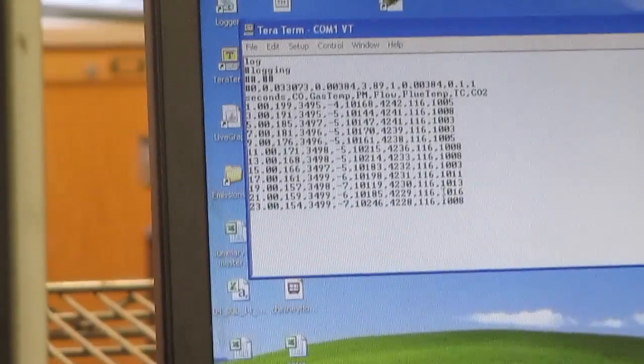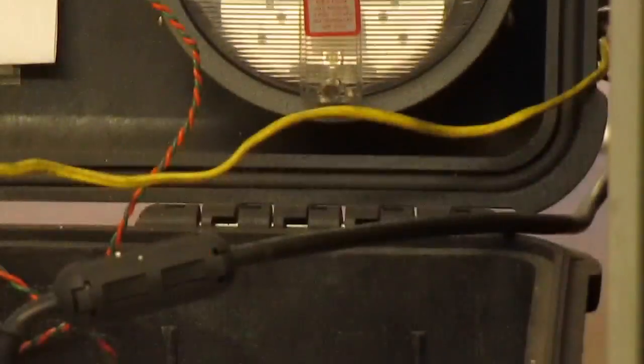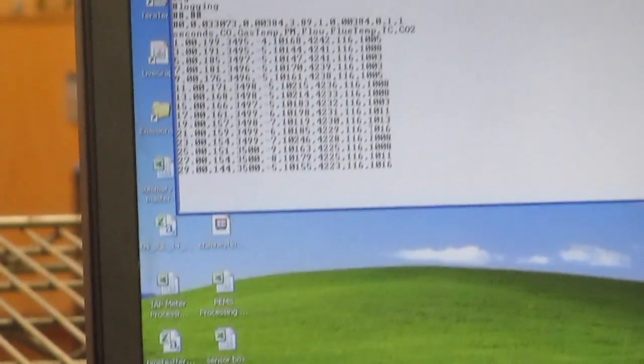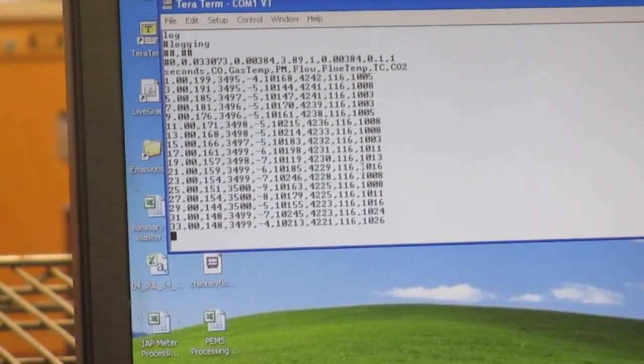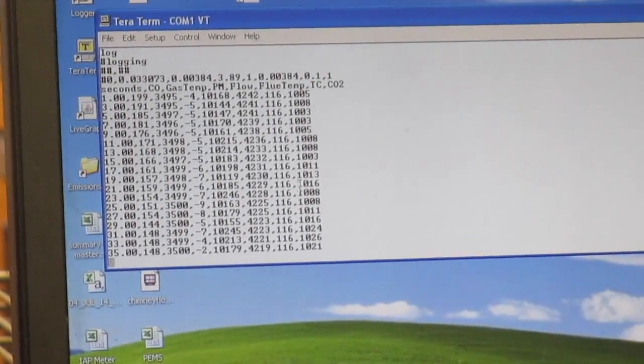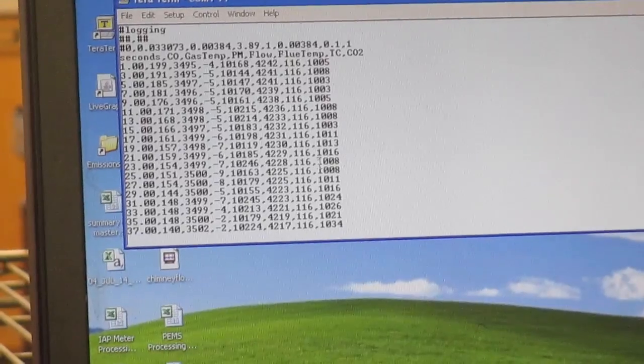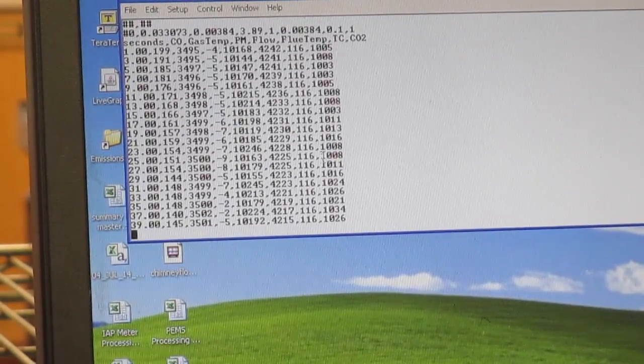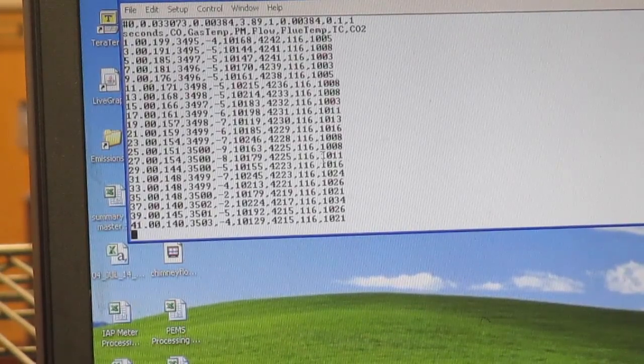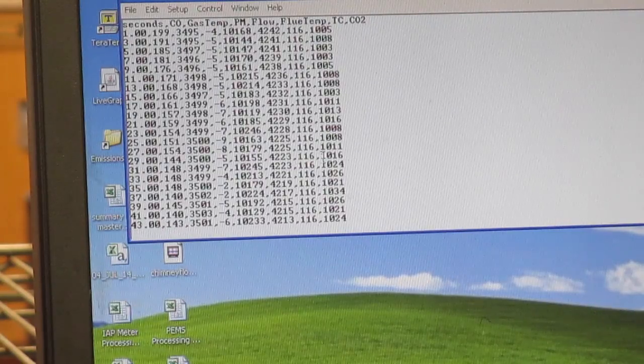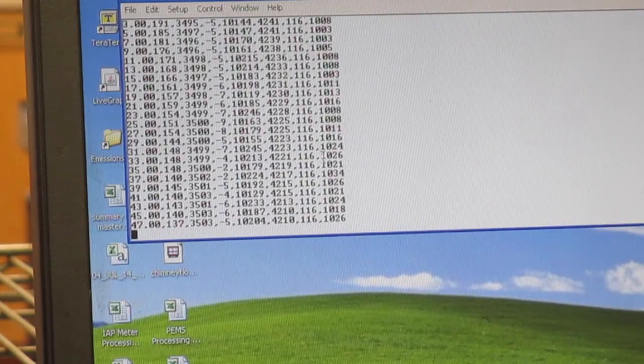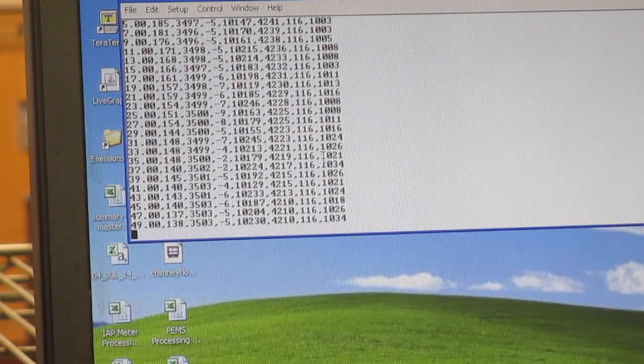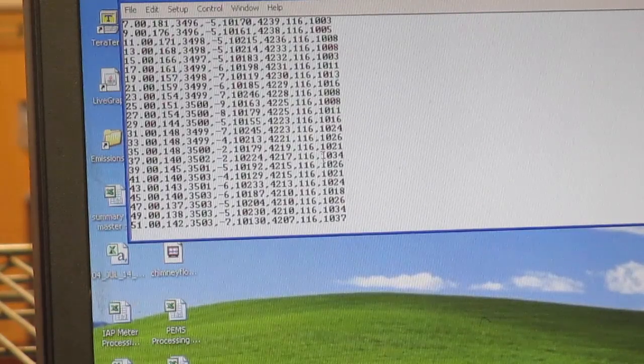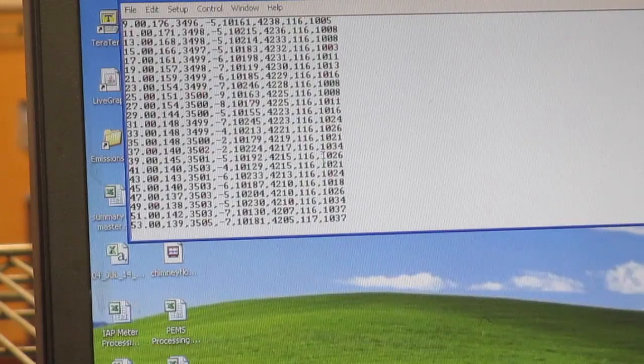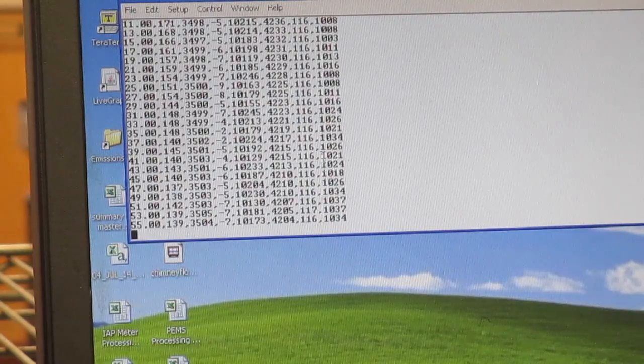So with this sensor box, all the sensor boxes that include the Magnehelic, the Excel software is written to calibrate the digital pressure sensor based on the analog Magnehelic only when the blower is turned on between 1 and 4 minutes after the sensor box is turned on. Sensor box is running right now, and after 1 minute I'm going to turn on the blower.